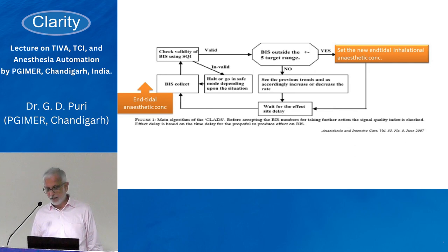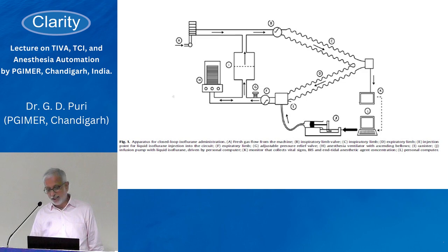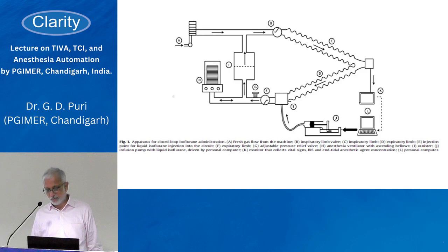In addition to BIS and heart rate/blood pressure monitoring, we added end-tidal inhalation anesthetic concentration monitoring into the algorithm. If end-tidal concentration was not as required, the anesthetic delivery was changed. We used syringe pumps to deliver isoflurane into the expiratory limb — similar to the Anaconda system used for ICU sedation. This allowed us to control isoflurane anesthesia using our closed-loop anesthesia delivery system.